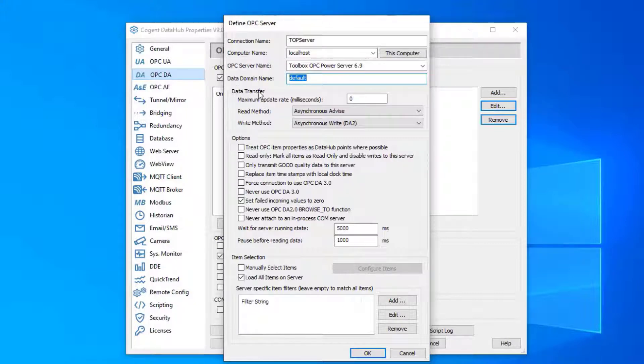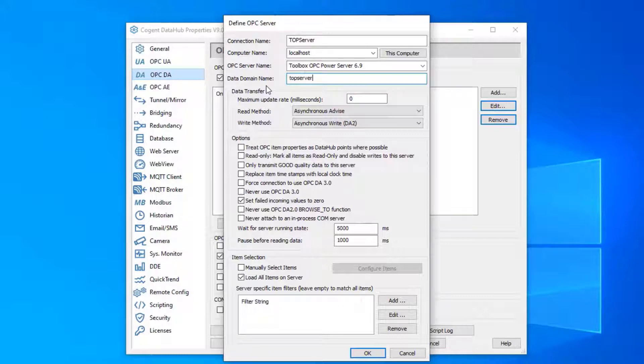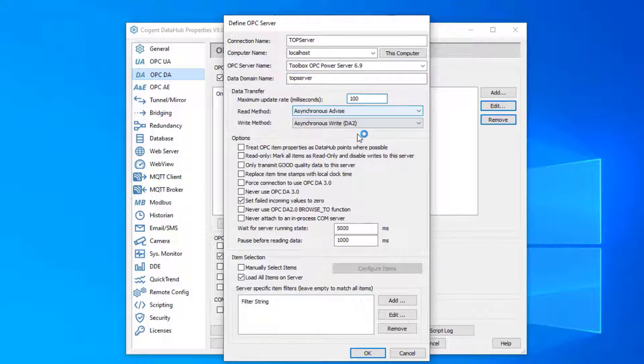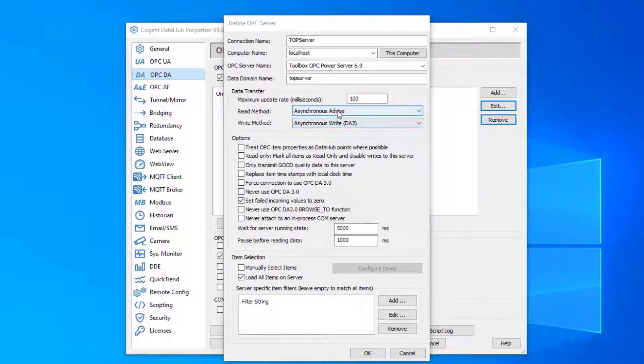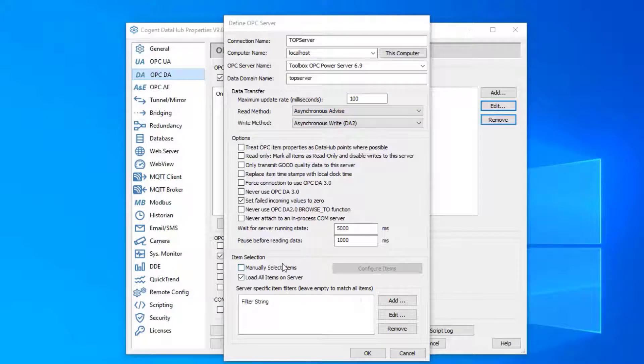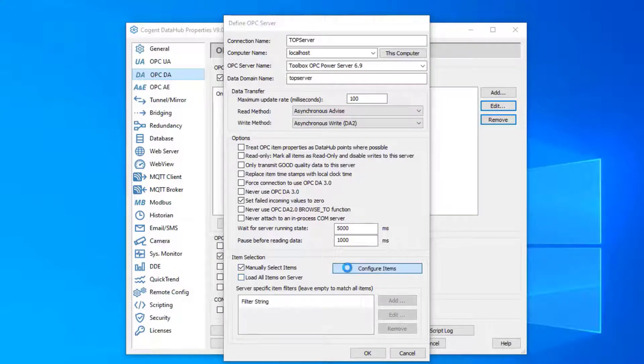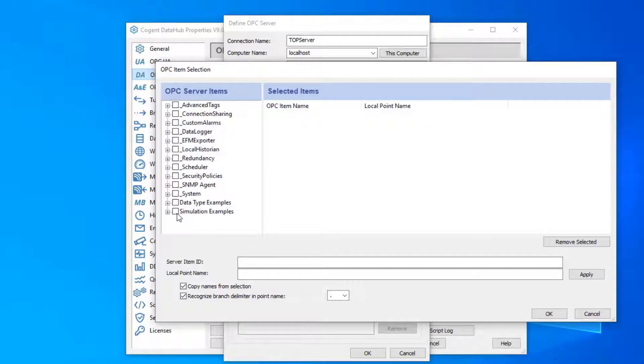Think of data domains like just a group of data. So I'm going to call this group 'top server' and this will be part of the tag name in the data hub. We'll scan the OPC server at 100 milliseconds. We're going to subscribe to the tags and I will choose a subset of the tags to monitor with data hub.